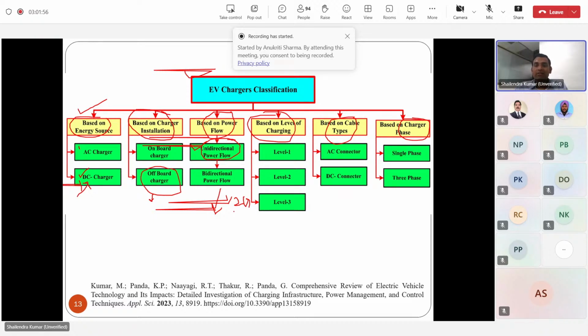Based on level of charging, chargers are categorized as level 1, level 2, or level 3, and based on connector type as AC or DC connectors. Based on number of supply phases, slow chargers can be integrated with single phase, but semi-fast or fast charging requires 3-phase supply. Otherwise, single phase can draw a maximum of 16 amperes per socket, even if you parallel them. So you cannot go for high power stations with single phase supply.